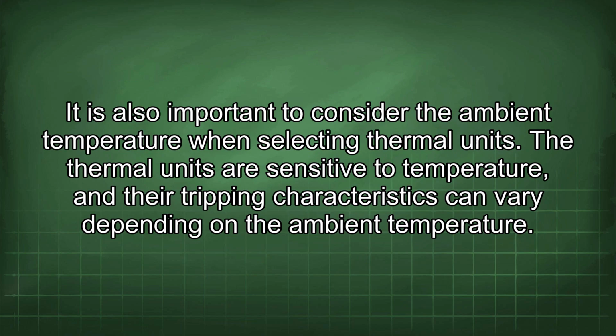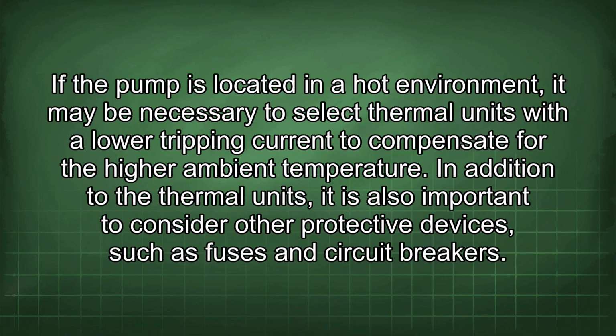It is also important to consider the ambient temperature when selecting thermal units. The thermal units are sensitive to temperature, and their tripping characteristics can vary depending on the ambient temperature. If the pump is located in a hot environment, it may be necessary to select thermal units with a lower tripping current to compensate for the higher ambient temperature.